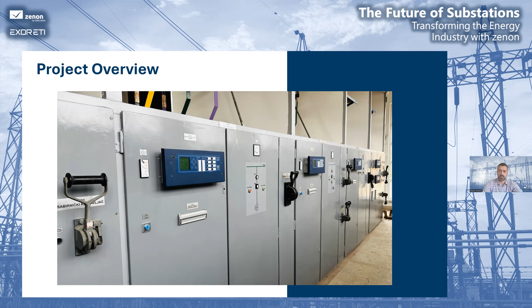Here is the overview. The high voltage 110 kV side consists of 6 bays: 2 overhead lines plus 4 transformer bays. Primary equipment replacement took place here, a new power transformer was added, and a complete substation automation system was implemented. On the medium voltage side, we have the 35 kV part with a new substation automation system and relay protection, but old primary equipment. On the 20 kV side, it's a brand new switchgear that also has a substation automation system included.